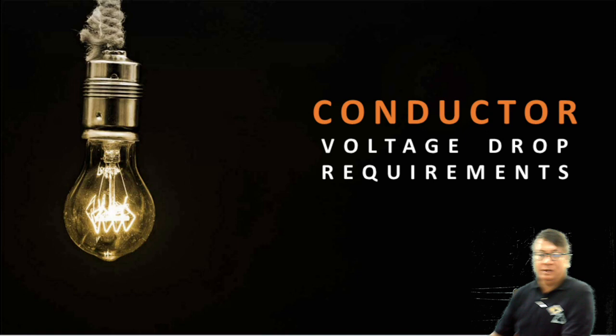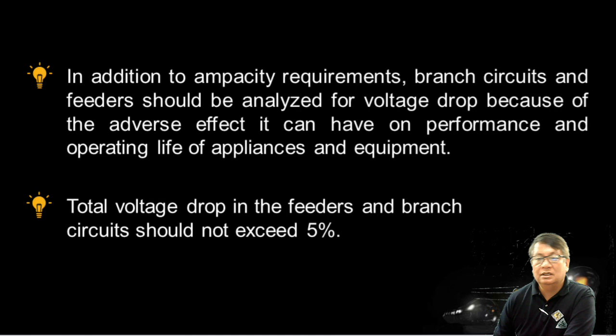What are the requirements for voltage drop? Okay, we have this. Ampacity requirements: circuits and feeders should be analyzed for voltage drop because of the adverse effect. And total voltage drop in the feeders and branch circuits should not exceed 5%. So the voltage drop in our conductor or cables must not be too high, because if it exceeds 5%, it will not qualify for our actual design.